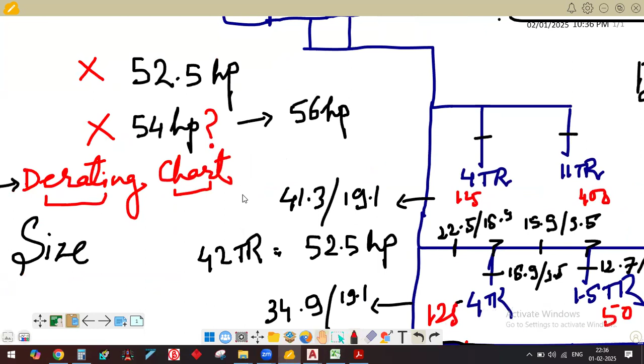Now suppose next I need to calculate. We have used this table, this table, and this table. Now we have to use this table: outdoor main header pipe size below 90. Now what is the HP? Suppose I have 56 HP. For 56 HP, my maximum pipe size is 41.3, 19.1. That means it is talking about this pipe size.